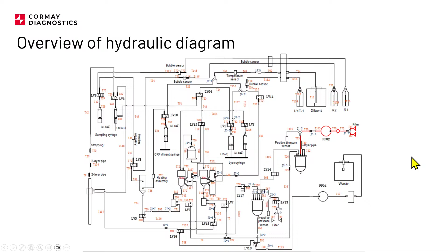Later, of course, after the measurements and before the measurements, there are a few preparation steps or cleaning steps. So those chambers are rinsed. The analyzer is just adding diluent through this line, and removing it later, right? To rinse this and prepare it for the analysis. Later, the sample is added, and the process starts. The same thing happens in the WBC and RBC, just to make sure that there will be no carryover from the previous analysis. So there are before and after cleaning steps, step by step. I believe this is also explained in the service manual. And this is just how the whole measurement is done.